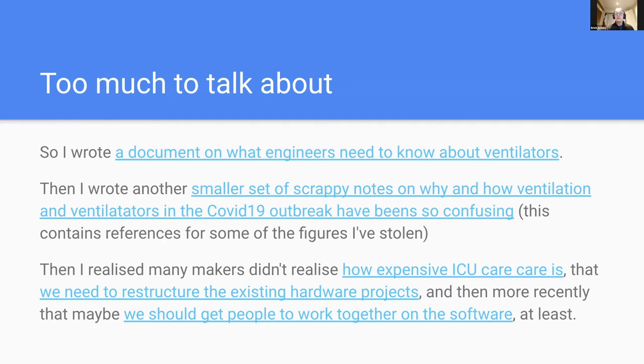That's guaranteed to be the situation. And if they are able to find nurses, they're going to be extraordinarily inexperienced. Any ventilator we produce needs to be capable of getting a patient better as quickly as possible, because while they're stuck on the ventilator, the entire healthcare system is hemorrhaging resources — which means other patients are suffering and resources are diverted away from public health measures. Secondly, if we're making ventilators for the pandemic, we need to be cognizant that these are going to be operated by inexperienced teams.